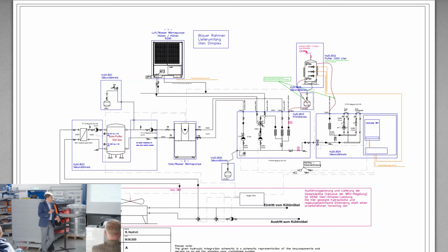The main device, the air-to-water heat pump, can support this main device, because the idea is to recover as much energy from the cabinets as possible, but sometimes if we don't have enough capacity from this, we can use this one as a backup or additional heat source. We also have the possibility to raise the temperatures with electrical heaters built into the buffer on the upper side.